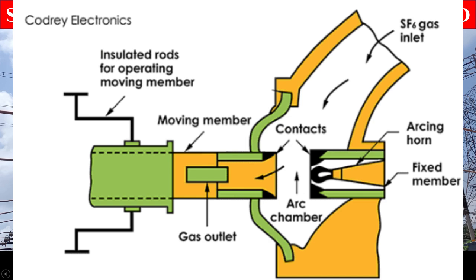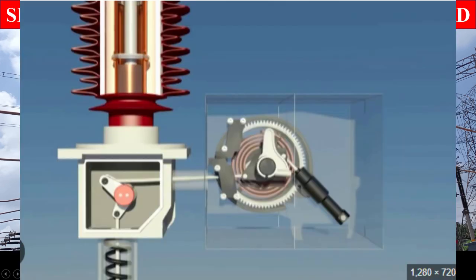The fixed contact is a hollow cylindrical current-carrying contact fitted with an arc horn. The moving contact is also a hollow cylinder with rectangular holes in the sides to permit the SF6 gas to let out through these holes after flowing along and across the arc. The tips of the fixed contact, moving contact, and arcing horn are coated with copper tungsten arc-resistant material. Since SF6 gas is costly, it is reconditioned and reclaimed by a suitable auxiliary system after each operation of the breaker.